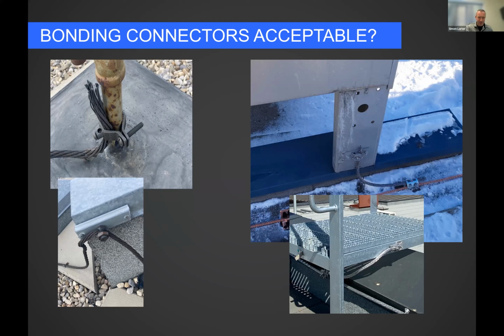That split bolt fitting on a piece of strut on a piece of galvanized curb, also not a listed bonding fitting for lightning protection. Did the cable fit through it, at least in that case? Yes, it did, but that's not a listed lightning protection fitting.